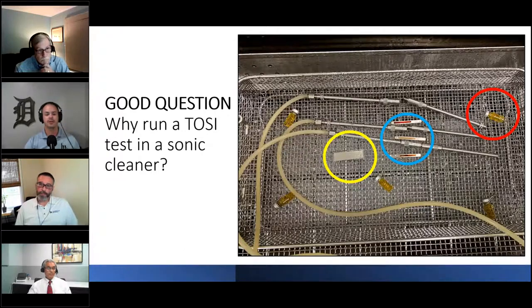Remember, our good question was why run that TOSI test in the sonic cleaner? We have to ask ourselves, like Seth said, what are we using this machine for? Is the ultrasonic being used to just clean regular instruments? How does that ultrasonic work? It works by way of cavitation or ultrasonic energy. In this picture, you see in that yellow circle a TOSI test. This came back completely clean after the cycle was ran, so we know the ultrasonic was able to clean a clinically relevant test soil from a stainless steel instrument.